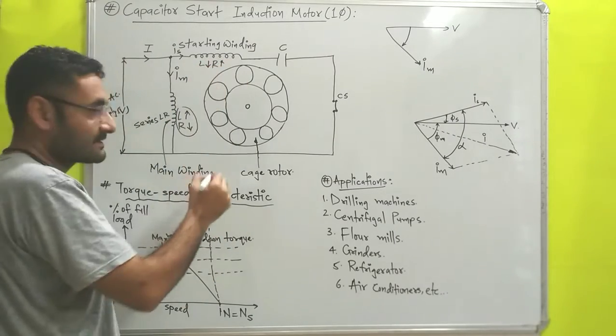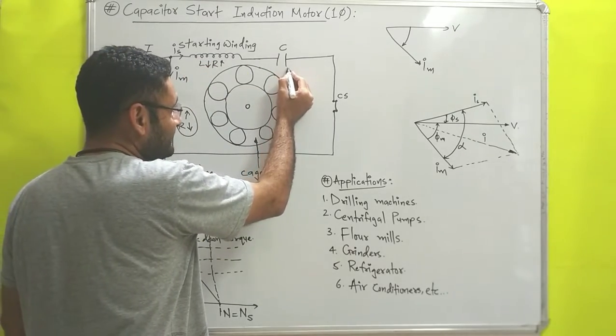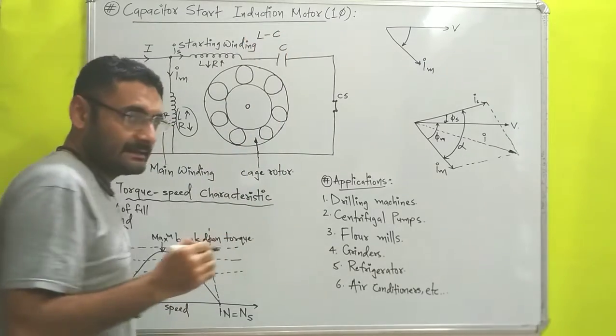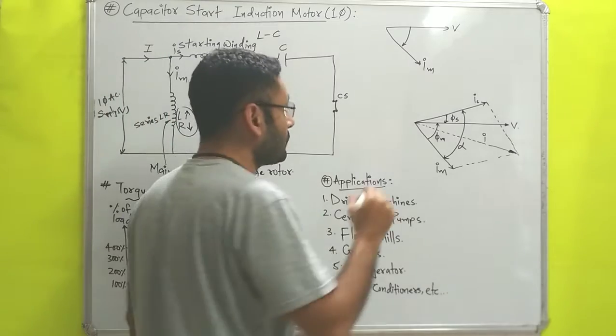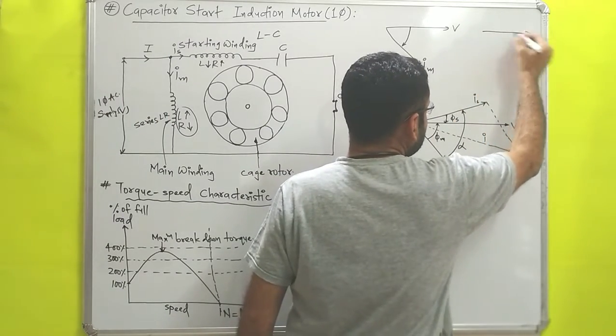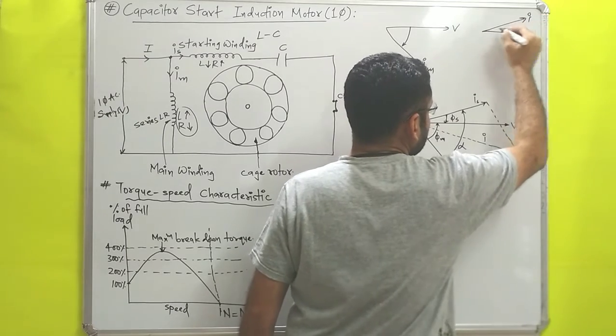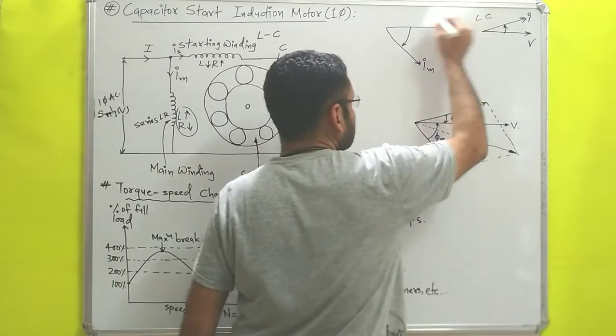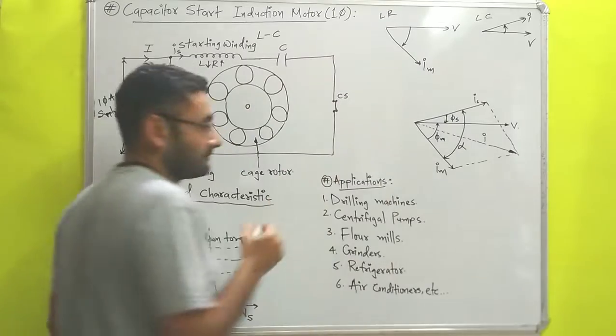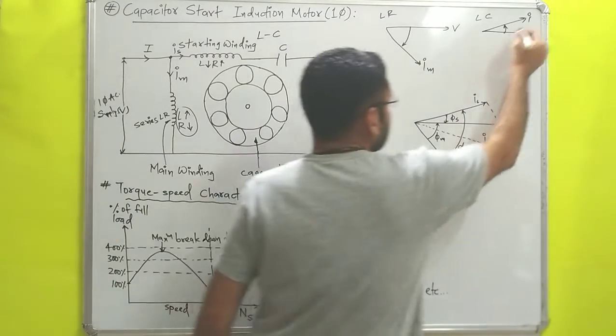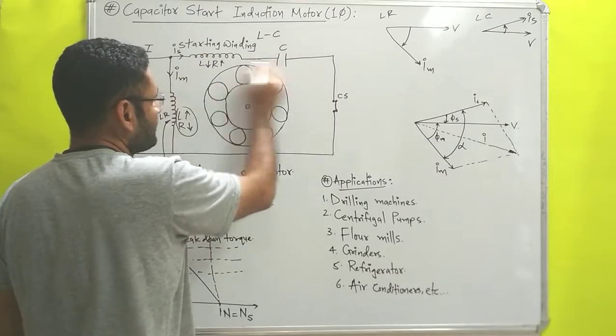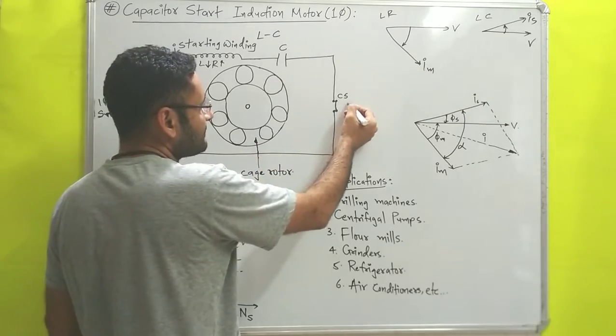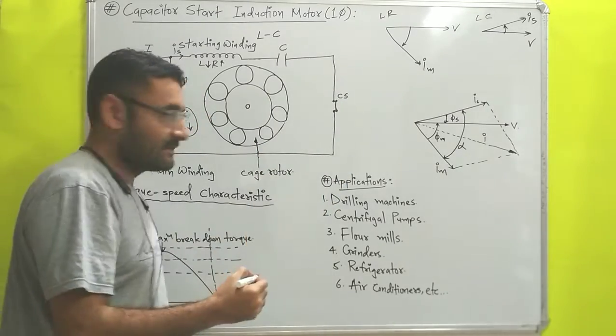The starting winding is designed with low inductance and high resistance, and it is connected in series with a capacitor. That entire branch forms a series LC circuit. For a series LC circuit, the current leads the potential by some phase angle. So Is is the current flowing from this series LC circuit, and it leads the supply voltage.